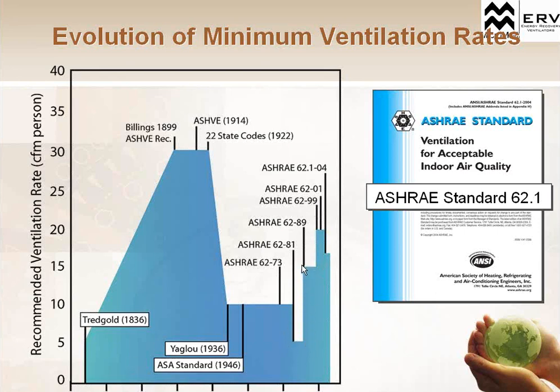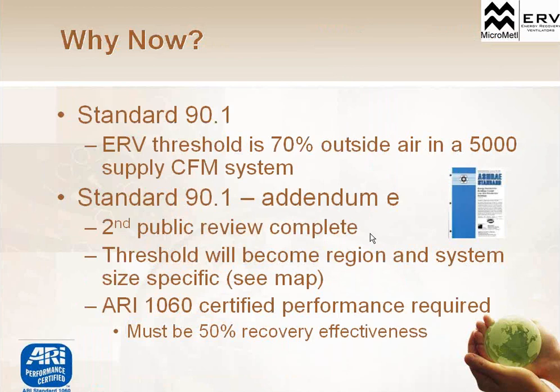So when they actually took a look at that, they raised the ventilation rates back to 15 CFMs. And for the next 10 or 20 years, we've kind of been bouncing between 15 to 20 CFMs per person in the space. So we've kind of honed in on what's a safe indoor air requirement on ventilation, and also what's applicable for the building, so that we can still maintain a certain level of energy efficiency bringing in that much outside air. So you can see the history of the ventilation rates. You can see here in 2004 is when they instituted ASHRAE 62.1, which is still our basis for today. They've built on that, but that's when we instituted 62.1.